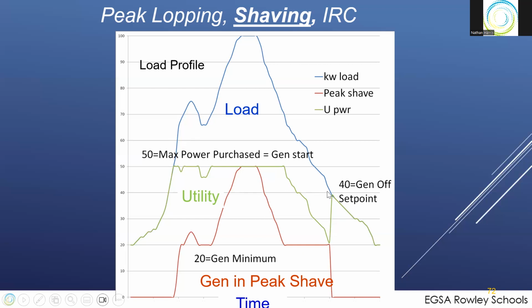So that's peak shaving. You have to know the power at the utility point in an analog value, or it could be digital, but it has to be a variable value of the watts at the utility tie point in order to make this work. But it's a good way to go, used very often, especially in areas of constraint or areas where you have high incident costs.